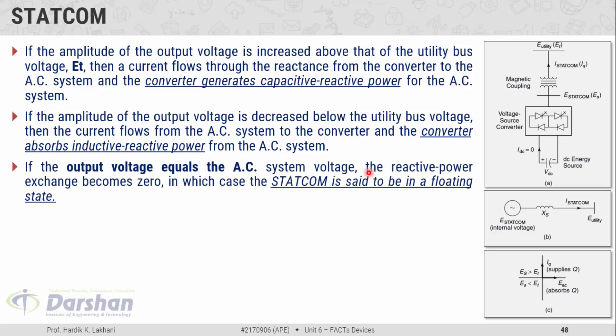If the output voltage equals the AC system voltage, that is when ES equals ET, the reactive power exchange becomes zero. In that case, the STATCOM is in the floating state — it neither absorbs nor injects reactive power into the system when the magnitudes of ES and ET are the same.